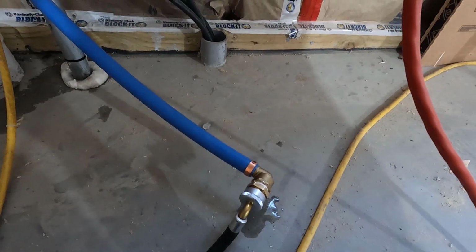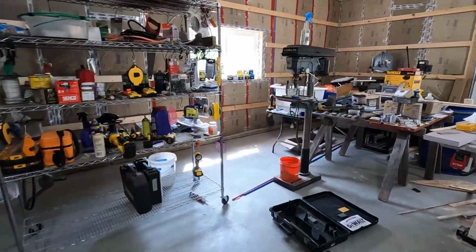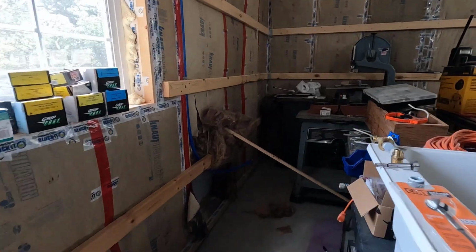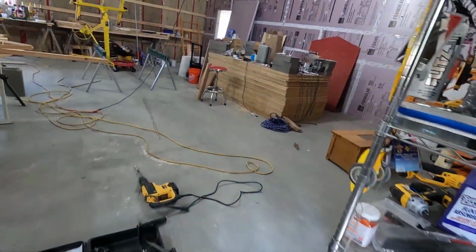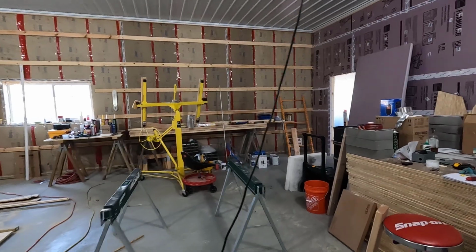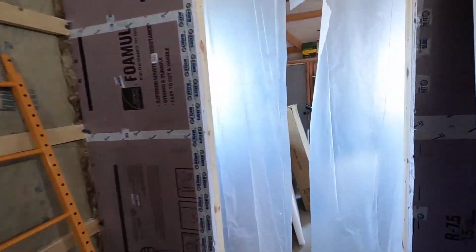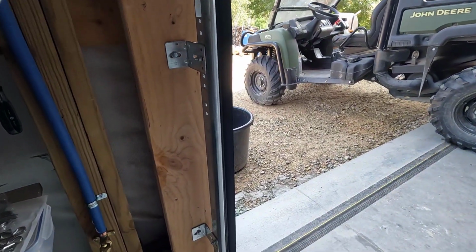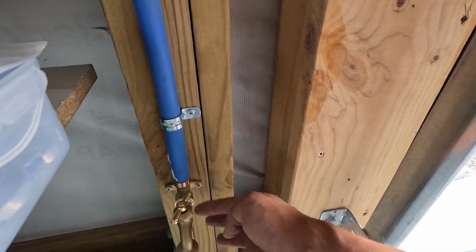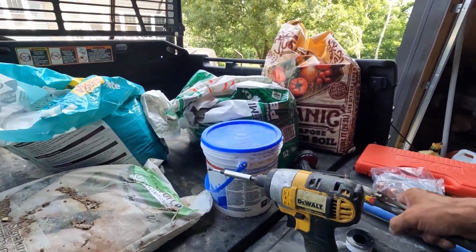Holy crap. Well, that stuff's not good. I'll have to dry that off, find out where that's leaking. That's not good at all. No leaks there. We had no leaks in the entire system, and the entire system was pressurized, so there shouldn't have been a leak at the hydrant there. No leaks here. Nice and dry. All right.